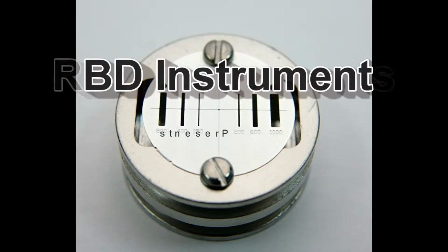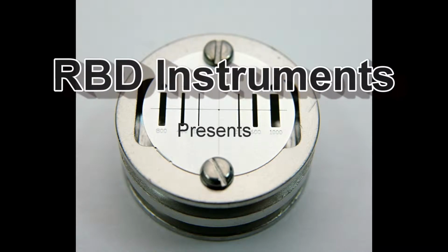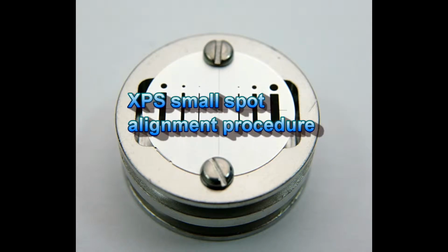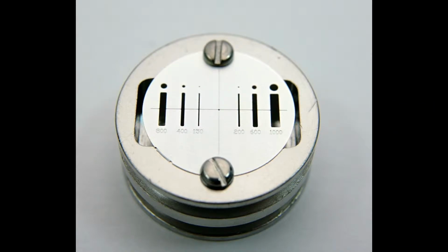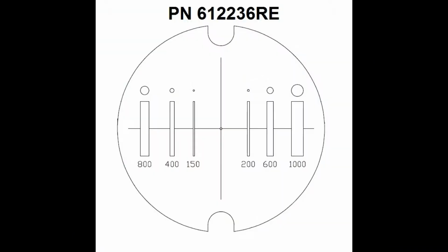This video will show you how to align the TV monitor microscope to the focal point of a Physical Electronics 5000 series X-ray photo-electron spectrometer. This procedure requires a slotted silver specimen standard, which is mounted on a recessed sample mount. The RBD part number is 612236RE.